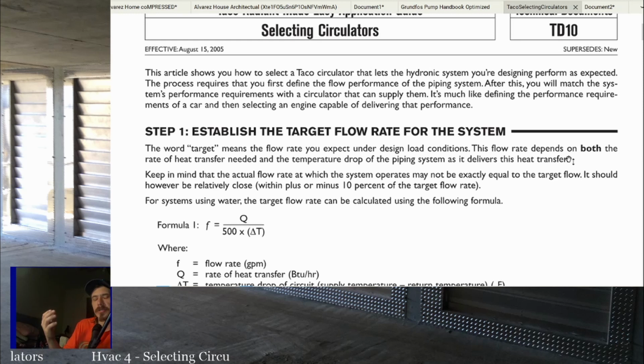And when we're sizing circulators, it's the same as sizing anything else. So with circulators, the easiest thing to do is think of feet of head as your static pressure in the system. It's the static pressure it has to overcome. So just like if you're sizing a fan for a house, if you got to be able to handle 1 inch static because your duct's long, circulators are the same thing. You got to handle so many feet of head because your piping's long.